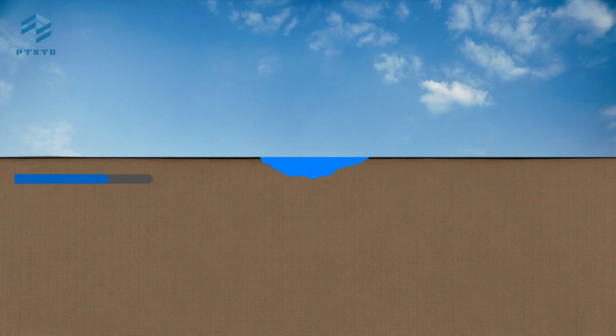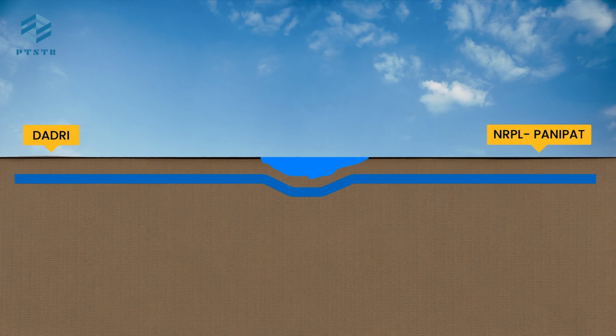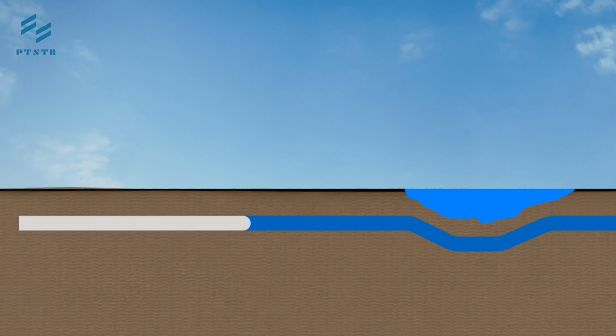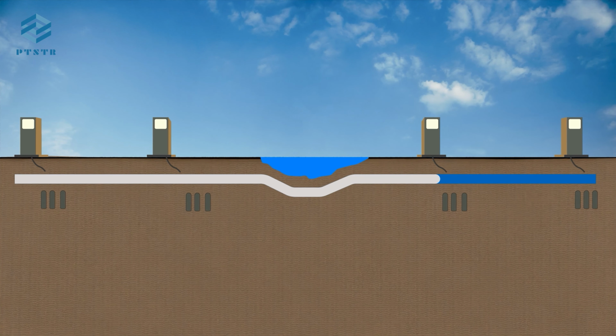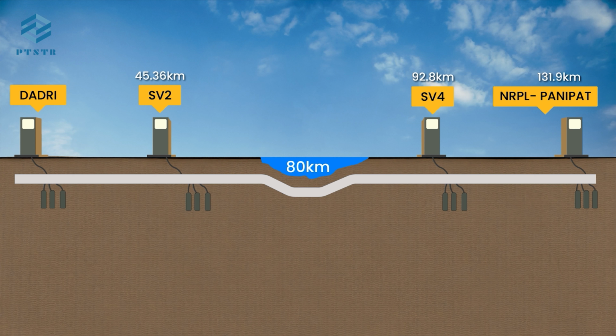The pipeline originates from Dadri and terminates at NRPL Panipat, with two stations at SV2 at 45.36 km and SV4 at 92.8 km, with a major river crossing chainage at 80 km. The pipeline is primarily coated with dual fusion-bonded epoxy and coal tar enamel. Protection against external corrosion is ensured through a permanent cathodic protection system, utilizing 4 transformer rectifier units or TRUs rated at 50V 50 ampere, each installed at Dadri, SV2, SV4, and Panipat.